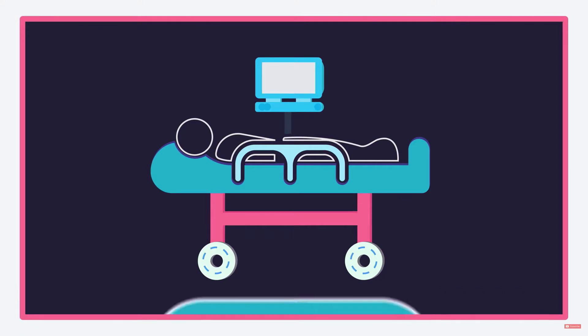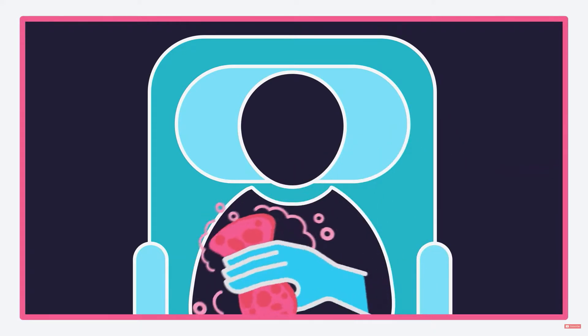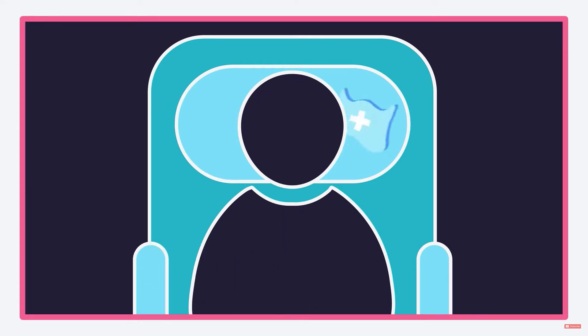The patient should be in a supine position with all limbs supported and chest exposed. No muscular work should be required on the patient's behalf to maintain the position. Prepare the skin: if dirty, clean with soap and water. Patients with chest hair should have hair at the electrode placement sites removed.